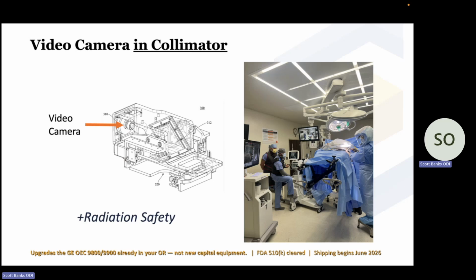While ODI was evolving this imaging platform, we had to change the collimator, that is the beam area limiting device that sits in front of the X-ray source. While we were there, we took the opportunity to put a video camera such that it's optically in line with the beam and perfectly registered. So this allows us two things. One is the radiation technologist can introduce the C-arm into the surgical field and align it with the patient under video control. That is, they can get things lined up without having to use X-ray and expose the patient or the surgical staff.